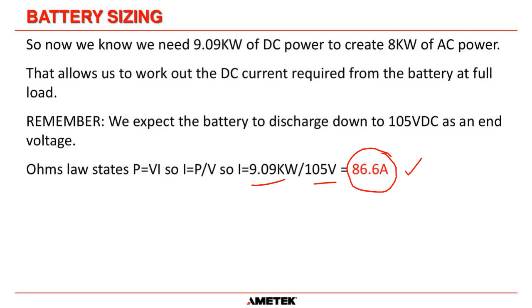So now that we know the kilowatts we need, it allows us to work out the DC current required for the battery at full load. And remember, we have to expect the battery to discharge down to 105 volts DC as an end voltage. So we use Ohm's law. Power is equal to volts times current, so current is equal to the power divided by the voltage. So current is 9.09 kilowatts divided by the end voltage of 105 volts. So we know our battery is going to have to supply 86.6 amps. That's how much the battery will need to supply to keep the inverter running at fully rated load to give you 8 kilowatts on the output of the inverter.